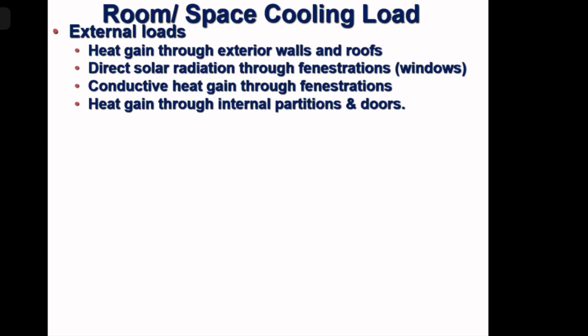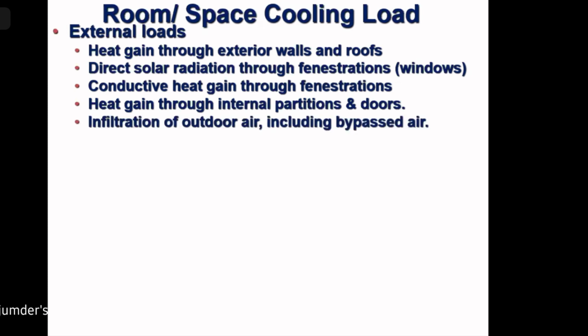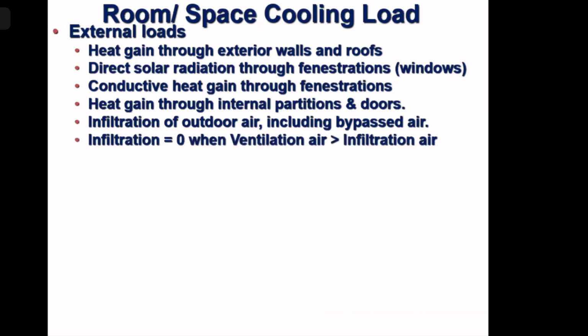Infiltration of outdoor air, including bypassed air. So if some air leaks inside the room, which normally will not, as we discussed, our basic intention is to make the room positive pressure. Then outside air will never enter the room, so infiltration will be zero. Next. Infiltration is zero when ventilation air is more than the infiltration air. That means the room is under positive pressure.